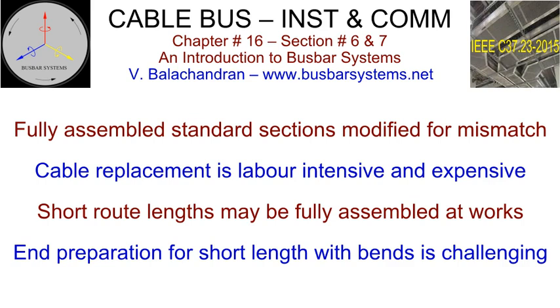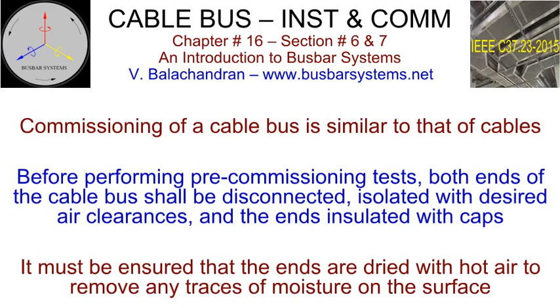The replacement of a faulty cable in a cable bus is a cumbersome and labor-intensive process. It can be very expensive and time-consuming. It may be possible to disconnect the faulty cable at either end and run the cable bus at a lower load till a sufficiently long maintenance/rectification period for shutdown is made available. Cable bus connections for short route lengths may be fully assembled at works with cables and installed at the site. End preparation of cables and negotiating them inside the cable bus of short length with several bends can be challenging at site. Commissioning of a cable bus is very similar to that of the commissioning of cables.